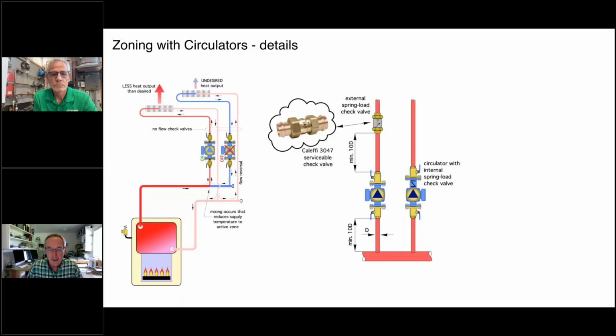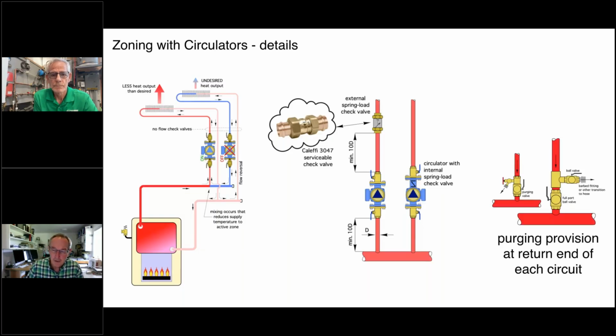And then on the return side of these zone circuits, if the piping is small enough, and I believe companies like Webstone, as an example, build these purging valves, which is basically an inline ball valve with a side port hose bib on it. I believe they go up to 2-inch pipe size. If you're working with larger pipe sizes, it's probably going to be something like this, where you can close the inline valve and open up that valve. The idea is during purging, the flow is going to go up through the circulator, out through the circuit, and then with this valve closed, it's going to push the air ahead of the water, for the most part, and push it back out of that circuit and into a purge cart of some sort, or just to a drain. So that's a way to expedite air removal out of that circuit.